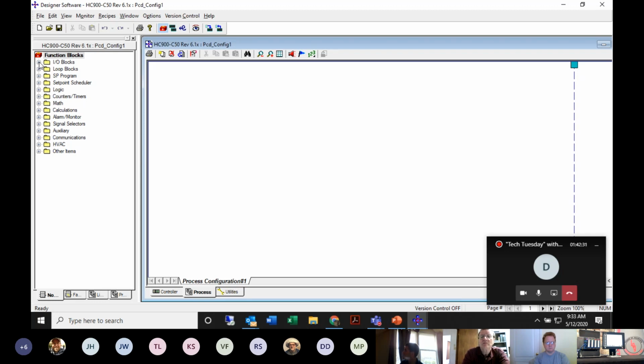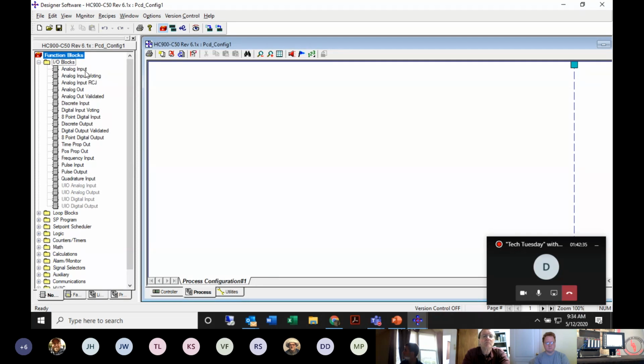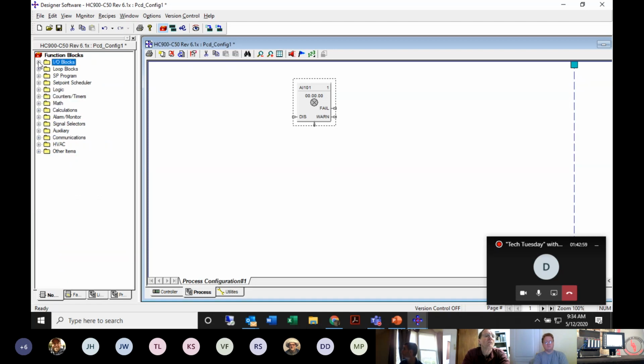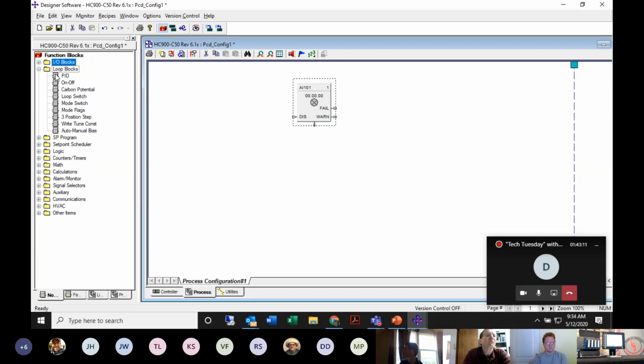If I was to start programming my PID loop, the very first thing I want to choose is my analog input. We have to have some way to feed the process variable signal back into my control loop. So I take an analog input, drag it out on the page, and now I have my analog input. In a couple of minutes, we'll go back and configure this, but let's complete the rest of our control loop for right now. The next thing is I have an analog input, but now I need a controller. I need my UDC to control the process. So let's choose a PID block, which mimics our UDC. We'll place that out on the paper.